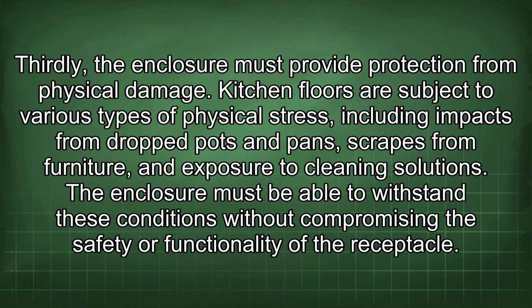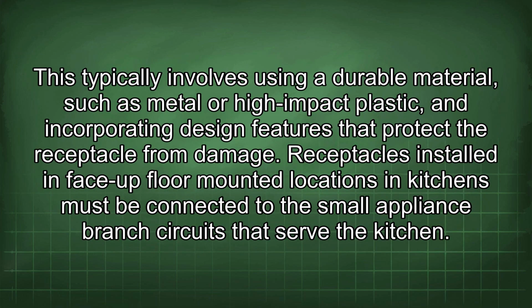Thirdly, the enclosure must provide protection from physical damage. Kitchen floors are subject to various types of physical stress, including impacts from dropped pots and pans, scrapes from furniture, and exposure to cleaning solutions. The enclosure must be able to withstand these conditions without compromising the safety or functionality of the receptacle. This typically involves using a durable material such as metal or high-impact plastic and incorporating design features that protect the receptacle from damage.